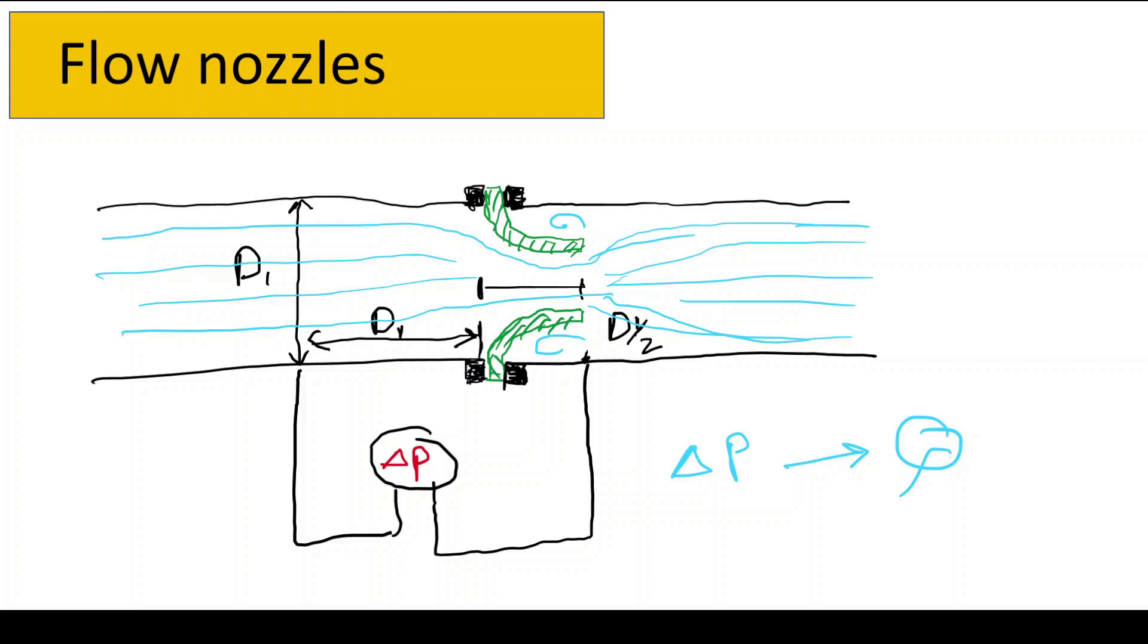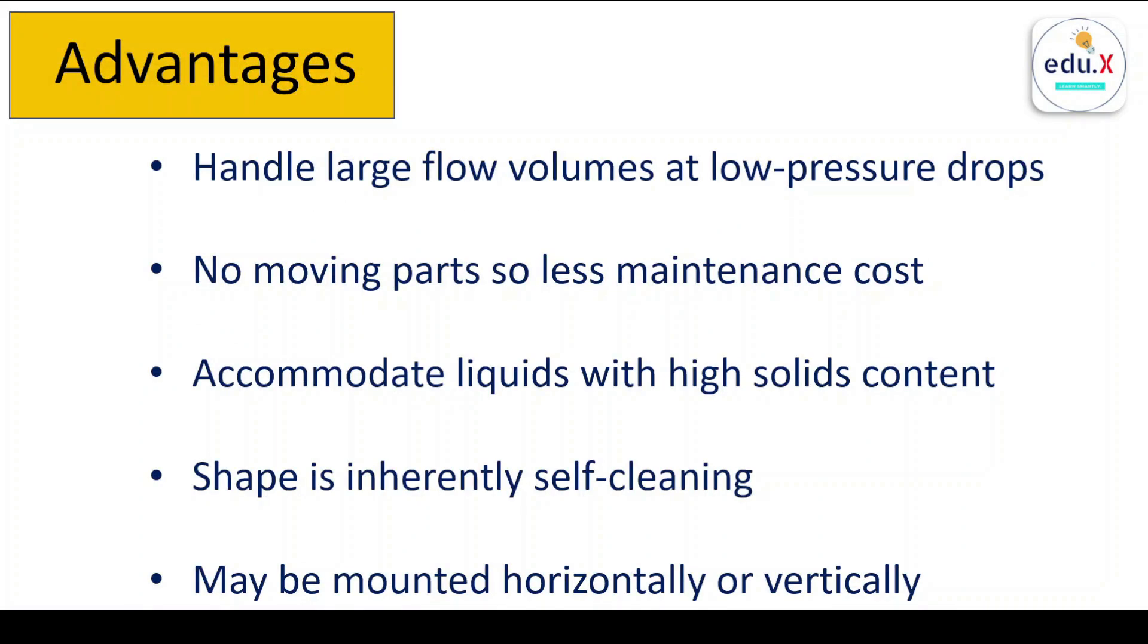So let's now discuss the general advantages and disadvantages of these two flow meter types. First, let's see the advantages. They can handle large flow volumes at low pressure drop. In our previous lesson that was related to orifice plates, compared to the orifice plates here we have minimum pressure drop. These types of flow meters don't have any moving parts so they require less maintenance. They can accommodate liquids with high solid contents that I just described earlier for the case of flow nozzles. And the shape is inherently self-cleaning, so there is converging throat and diverging section that will automatically clean the surfaces of this meter. And it may be mounted horizontally or vertically.